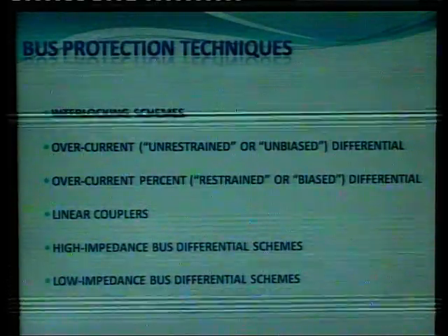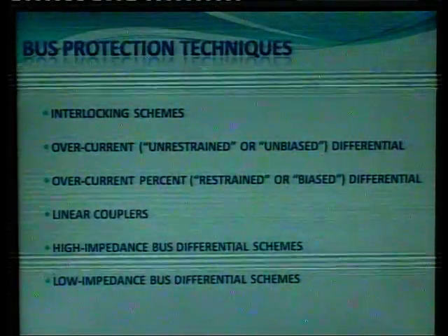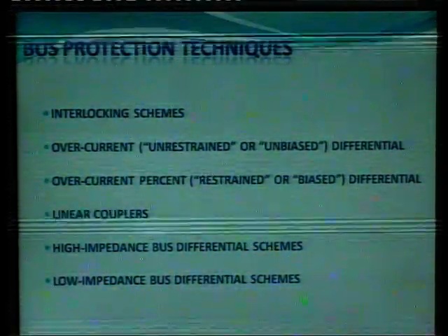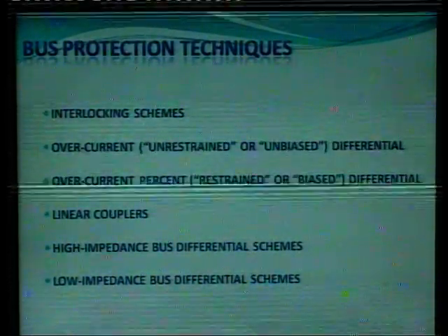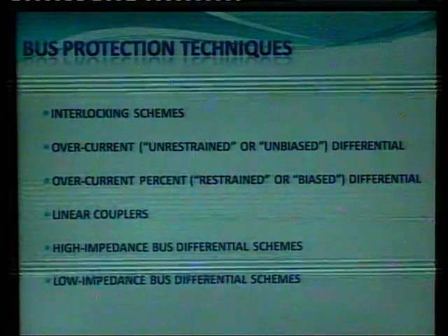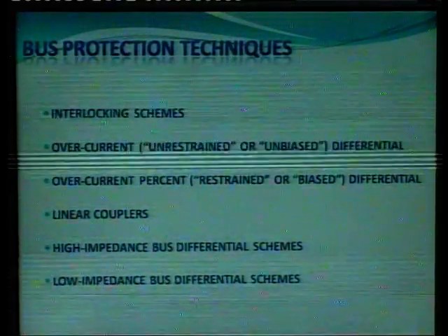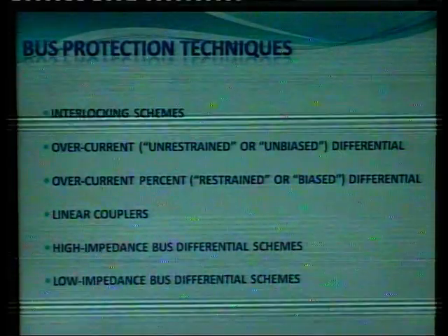So, these are some bus protection techniques: interlocking schemes, overcurrent, or you can say unrestrained or unbiased differential scheme, percent differential technique, linear couplers, high impedance bus differential scheme, and low impedance bus differential scheme.